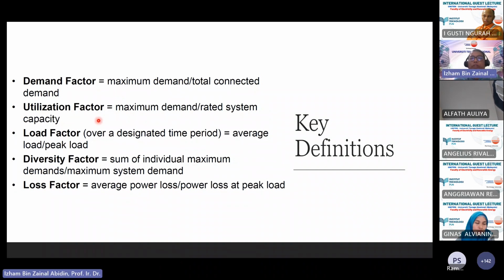Okay, so this is the demand factor. You also have what you call the utilization factor. That is the ratio of the maximum demand divided by the rated system capacity, which is what the system can actually handle. That covers how many percent of the resources it is actually using. You also have the load factor. The load factor is usually over a specific time, and it is the average load divided by the peak load. You also have the diversity factor. This one covers individual maximum loads. Let's say I have 10 different types of load connected, each with its own maximum demand. I combine those maximum demands and divide by the maximum system demand for the system itself. Then, of course, I also have the loss factor, which covers the average power loss and the power loss at peak load. All these elements need to be taken into account when you try to model the load and understand the load itself.